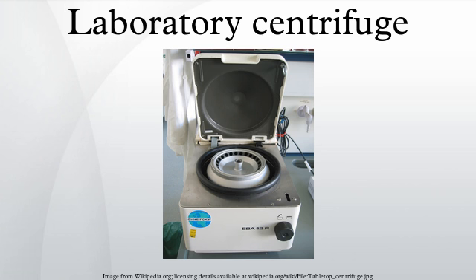Safety. The load in a laboratory centrifuge must be carefully balanced. This is achieved by using a combination of samples and balance tubes which all have the same weight, or by using various balancing patterns without balance tubes. Small differences in mass of the load can result in a large force imbalance when the rotor is at high speed. This force imbalance strains the spindle and may result in damage to the centrifuge or personal injury. Some centrifuges have an automatic rotor imbalance detection feature that immediately discontinues the run when an imbalance is detected.